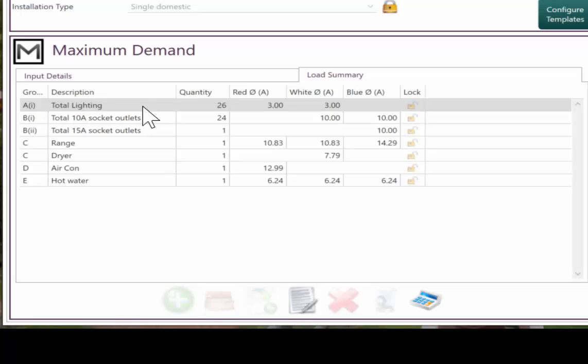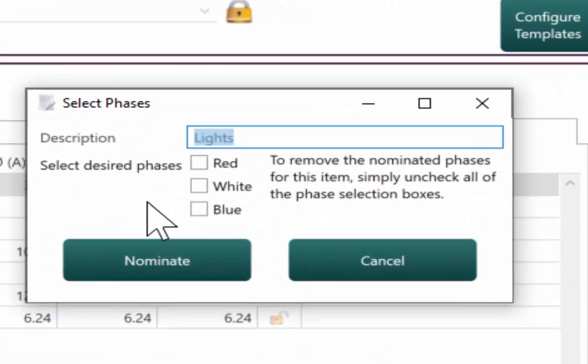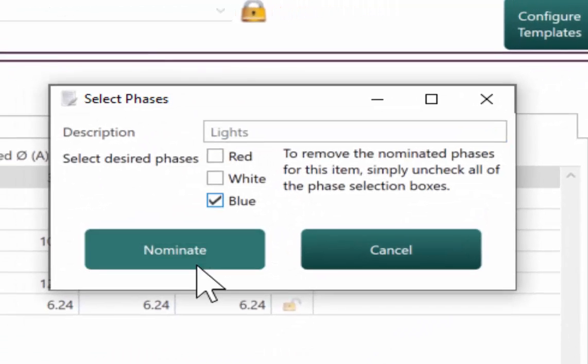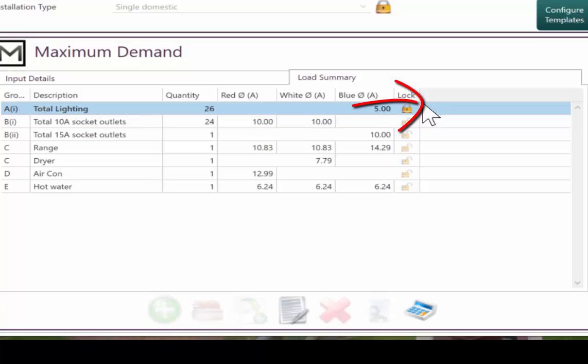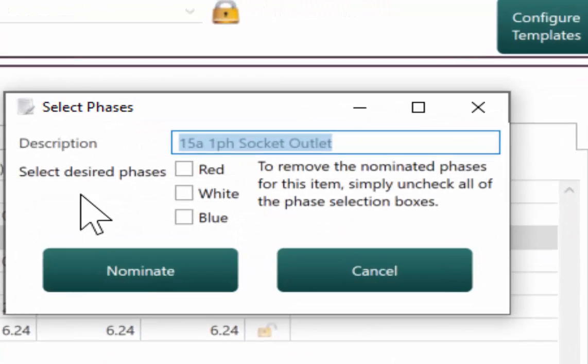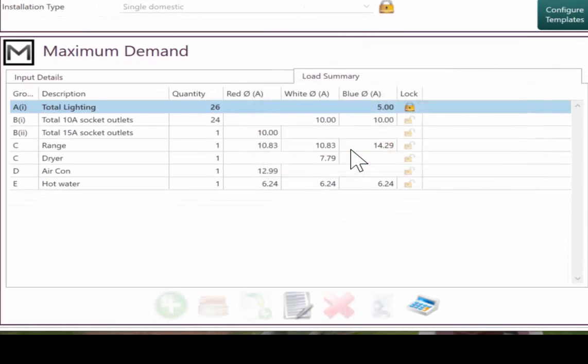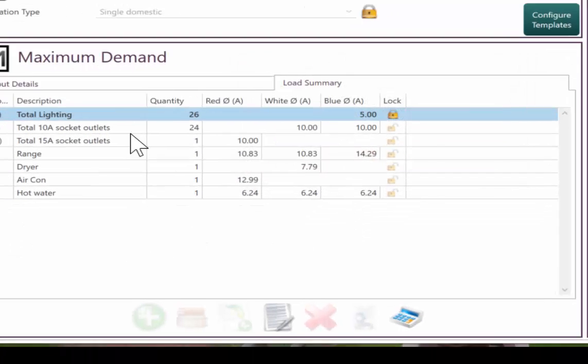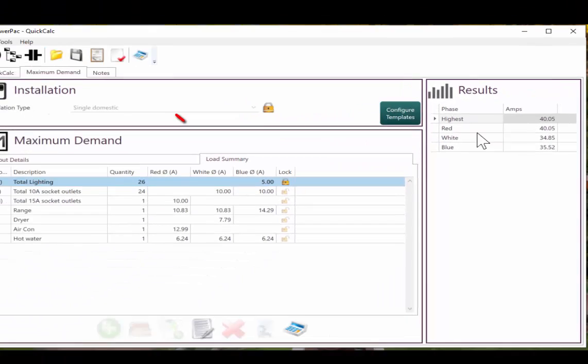So to match the standards example, all of the lighting has been put on blue phase. And as you can see, it's recalculated the maximum demand rules of 3 amps for the first 20 and then 2 amps for the next 20 after that. And also standards have put the 15 amp on red phase. So now that we've redone that balance, we can see that the highest rated phase is 40 amps.